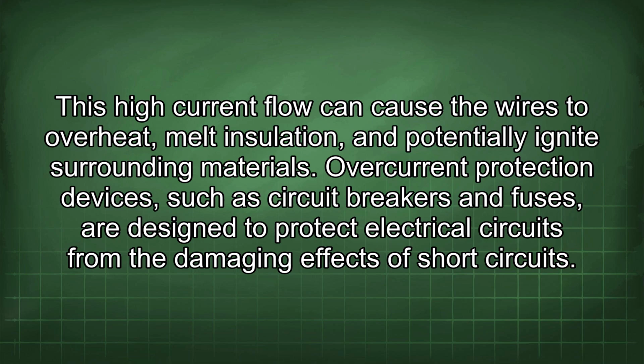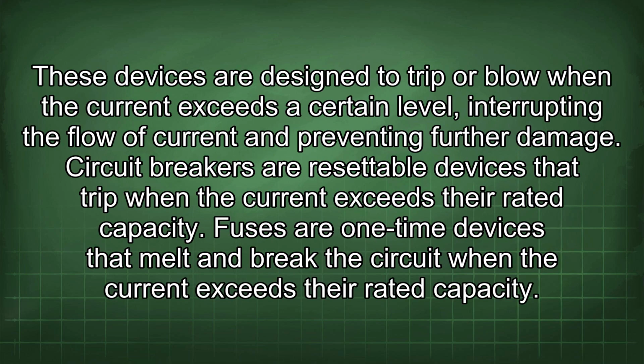Overcurrent protection devices, such as circuit breakers and fuses, are designed to protect electrical circuits from the damaging effects of short circuits. These devices are designed to trip or blow when the current exceeds a certain level, interrupting the flow of current and preventing further damage. Circuit breakers are resettable devices that trip when the current exceeds their rated capacity. Fuses are one-time devices that melt and break the circuit when the current exceeds their rated capacity.